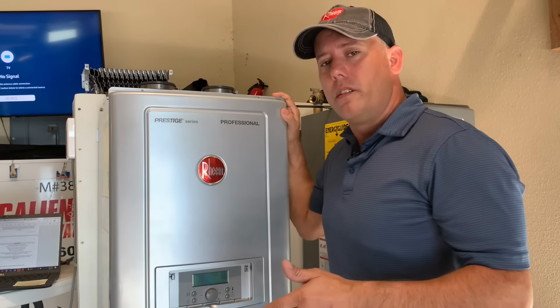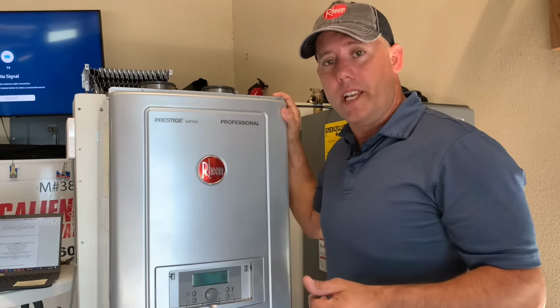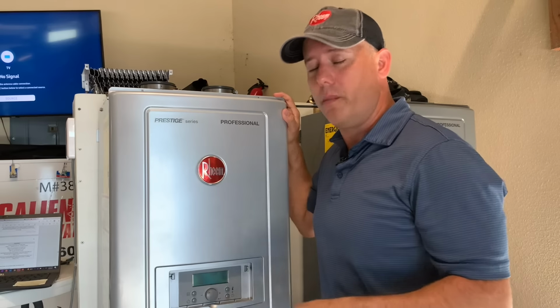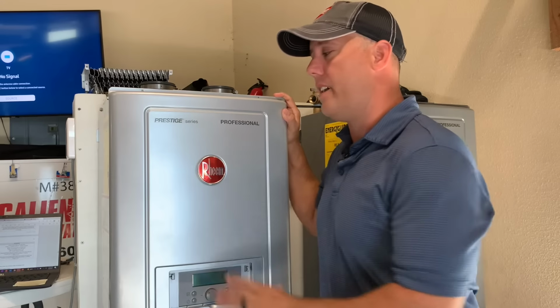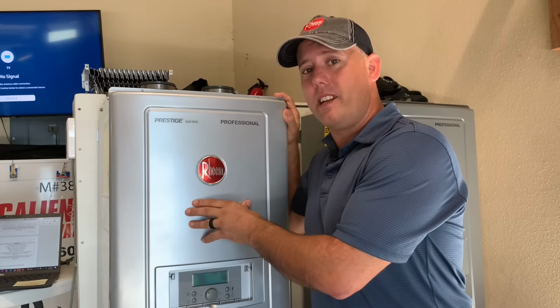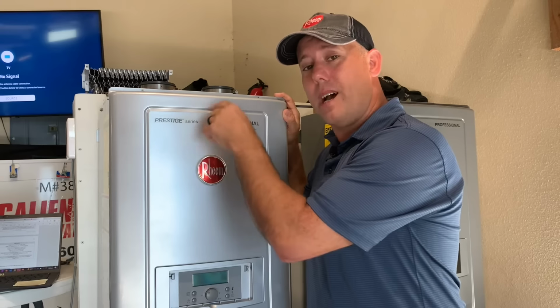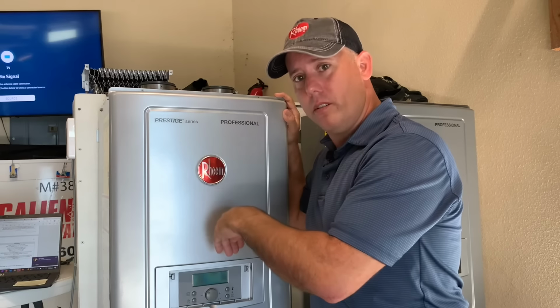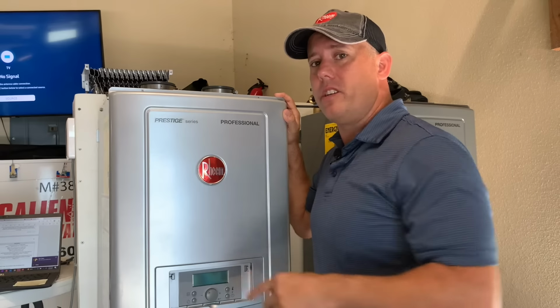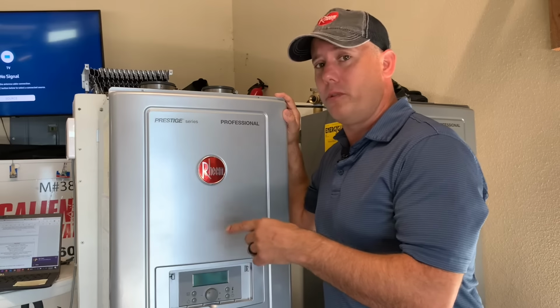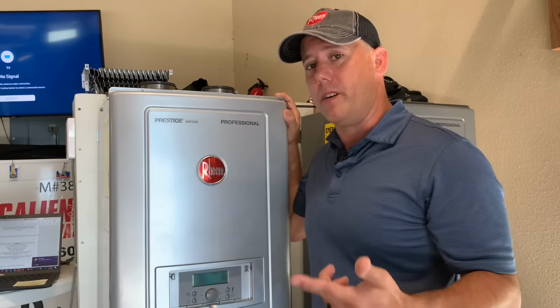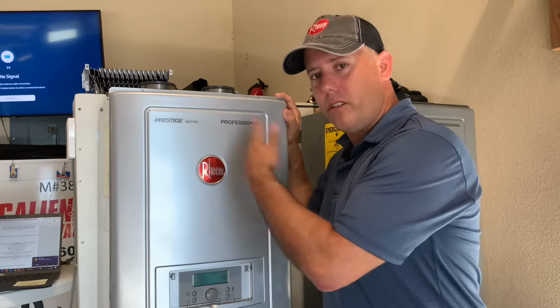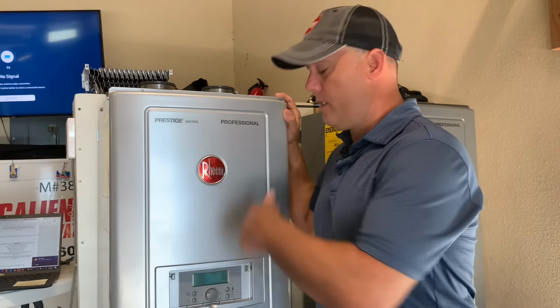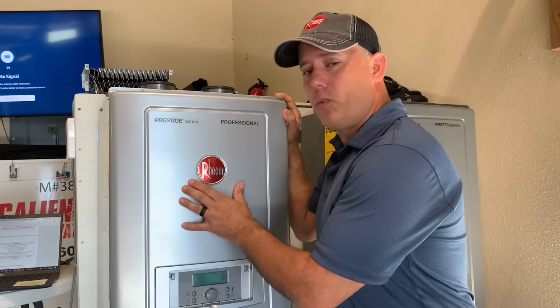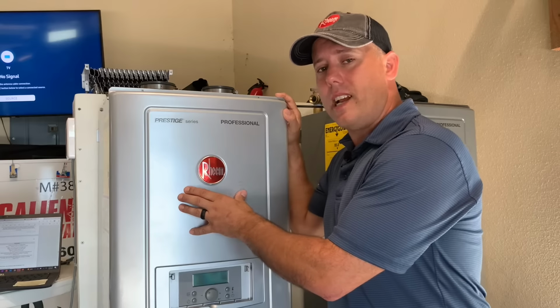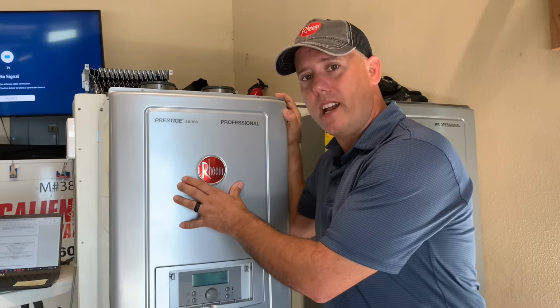Moving on. This water heater works like many other tankless water heaters. It's got a heat exchanger. It heats the water, it spits it out hot. We all get that. This one has a primary and a secondary heat exchanger. Primary heat exchanger being on top with a down fire burner. It's firing downward, okay? And then it has a secondary heat exchanger. Interestingly enough, when the water flows through this unit, it goes through the secondary heat exchanger first, gets warm, then it goes through the primary, gets really hot, and then it comes out. So that's how this works. And this is a current generation that's out right now. Today we're going to focus on this guy here.